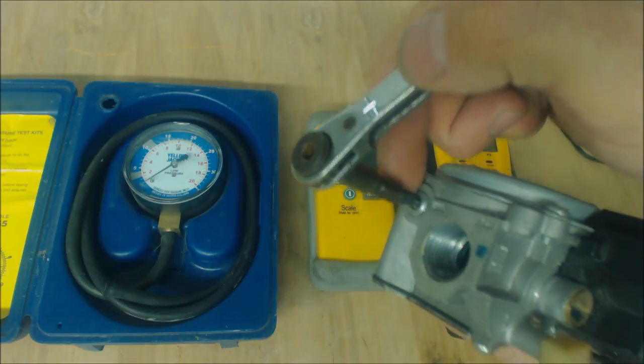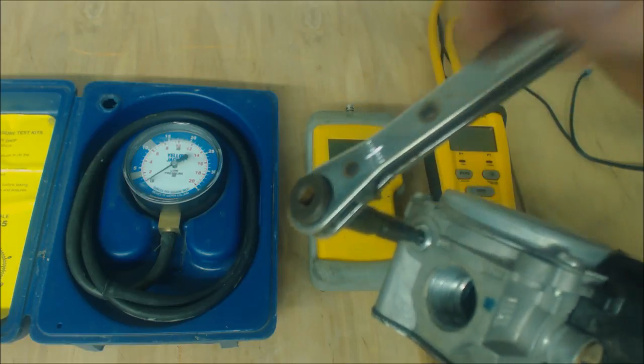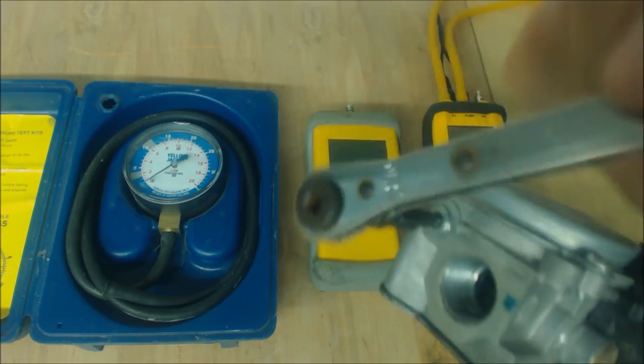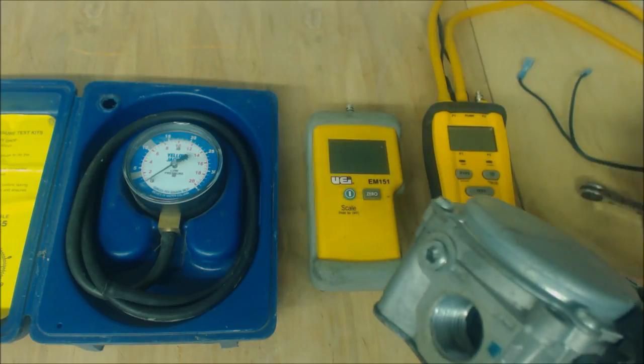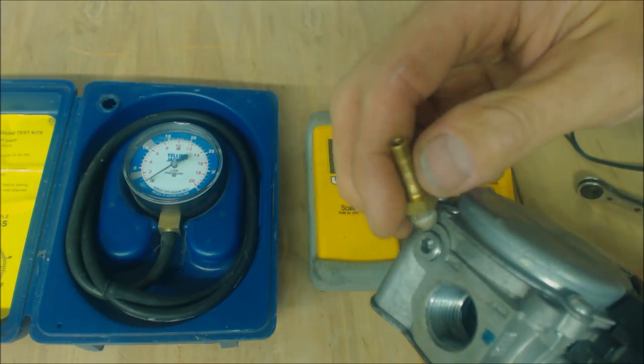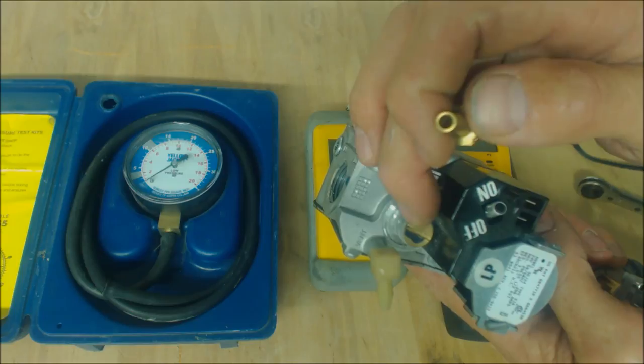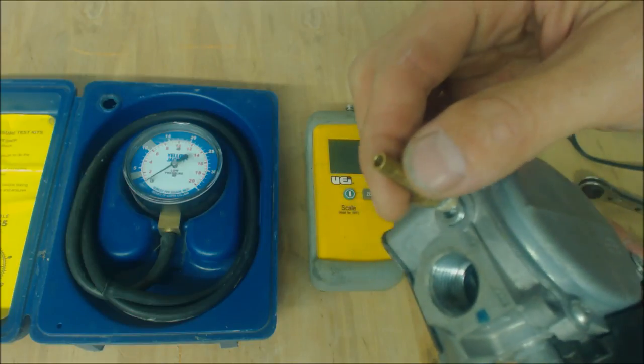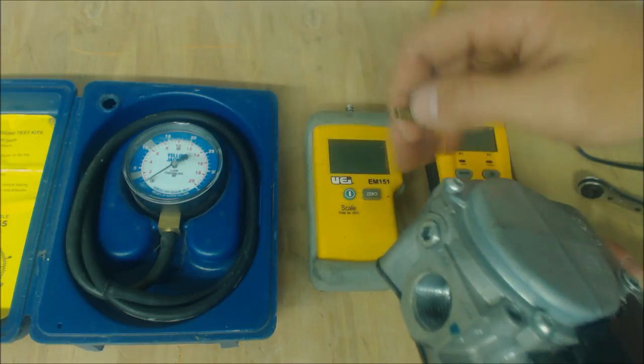Over here, we would turn the gas furnace off, take this off, and attach our brass barb fitting. This will give us our outlet gas pressure, which can be adjusted with this brass screw. We would check our gas pressure here.